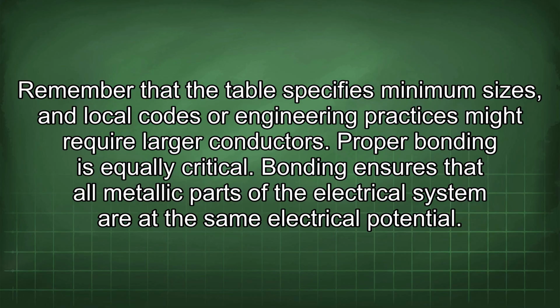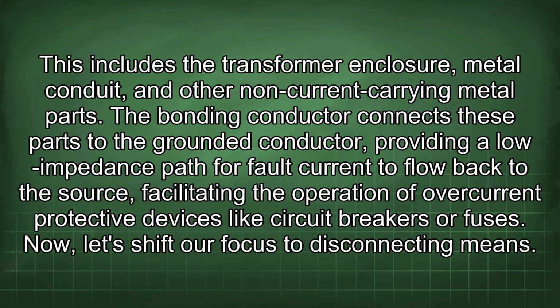Proper bonding is equally critical. Bonding ensures that all metallic parts of the electrical system are at the same electrical potential. This includes the transformer enclosure, metal conduit, and other non-current carrying metal parts. The bonding conductor connects these parts to the grounded conductor, providing a low impedance path for fault current to flow back to the source, facilitating the operation of overcurrent protective devices like circuit breakers or fuses.